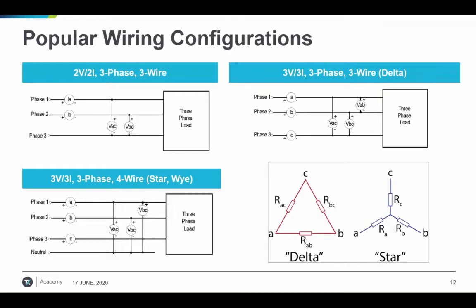The 3V3I configuration is called the three-watt meter method and uses three voltage and three current probes to make three-phase measurements. You can make per-phase measurements referenced to a neutral if available in a star configuration. If it is a delta configuration where neutral is not present, you make voltage measurements between phases, also known as line-to-line voltages. Other wiring configurations include one-phase two-wire using one voltage and one current probe — typically used for measuring the DC bus of the drive — and one-phase three-wire using two voltage and two current probes, only available for the input of the drive.